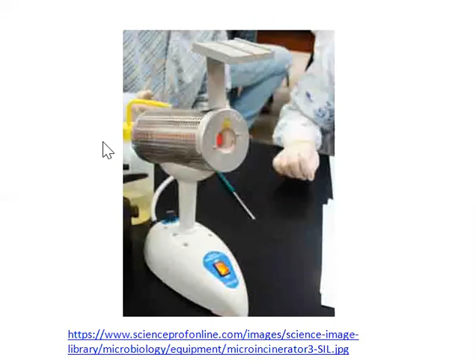For bacteria, there are small incinerators which are used, and they are called mini furnaces. In this picture, you can see a micro incinerator. It is also known as a Bacti incinerator. It is a device used in microbiology laboratories to sterilize small instruments. This sterilization instrument consists of a ceramic tube. Here you can see inside this there is a ceramic tube. It is surrounded by the metal, with a hollow portion between this tube and this metal at the center. When plugged in and turned on with the power supply, the micro incinerator can reach a temperature of 800 degrees centigrade or more, and it is sufficient to eliminate the microbes from the inoculating loop.